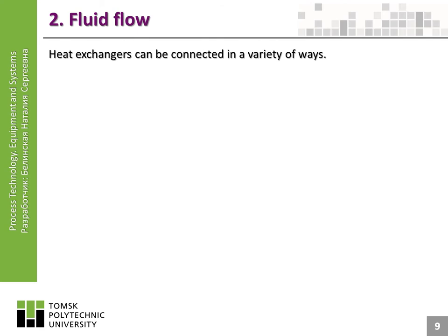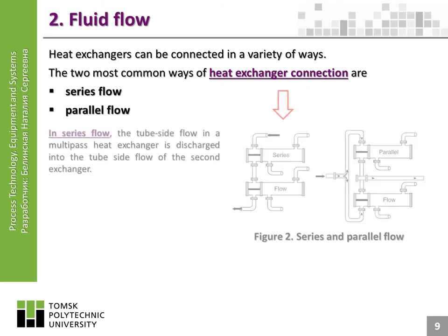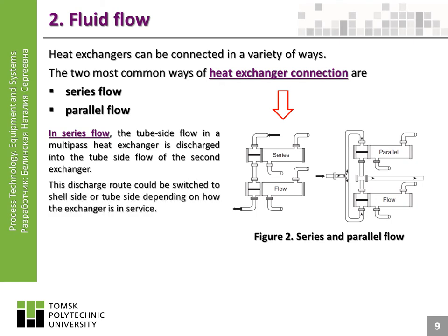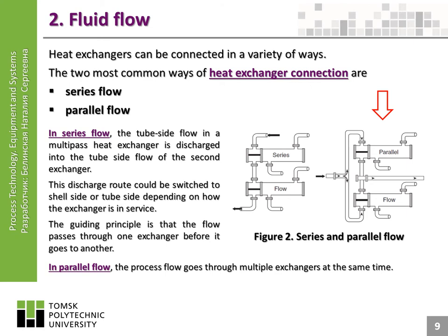Heat exchangers can be connected in a variety of ways. The two most common ways of heat exchanger connection are series flow and parallel flow. In series flow, the tube-side flow in a multipass heat exchanger is discharged into the tube-side flow of the second exchanger. The guiding principle is that the flow passes through one exchanger before it goes to another. In parallel flow, the process flow goes through multiple exchangers at the same time.